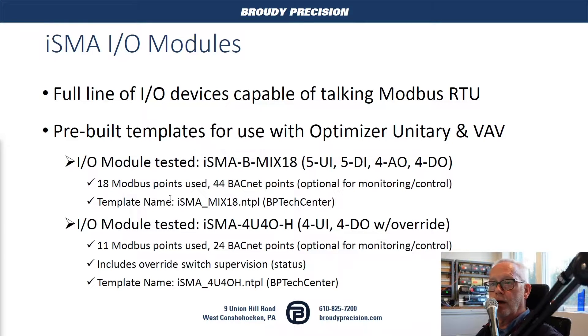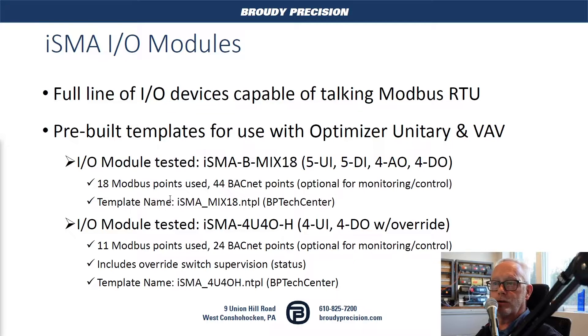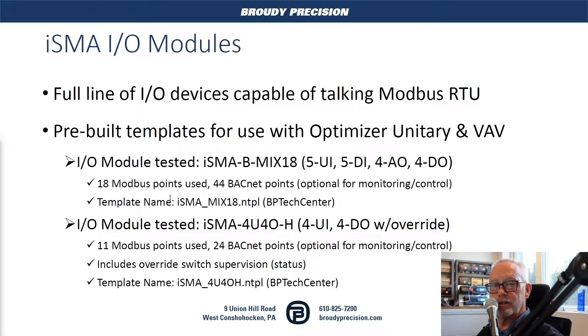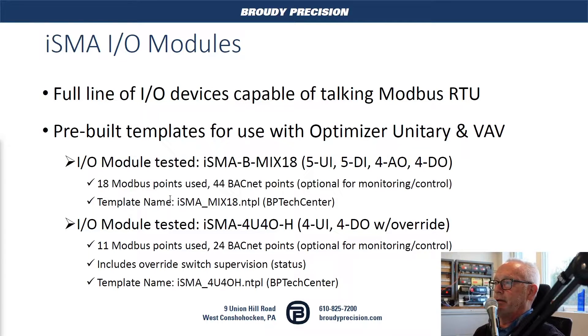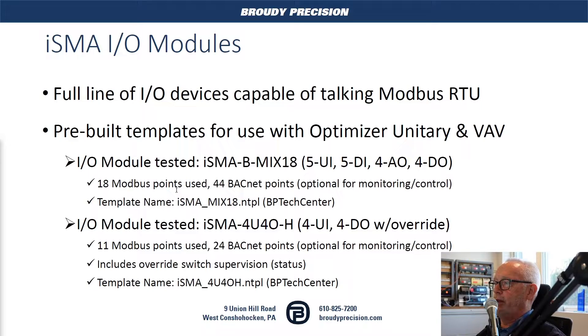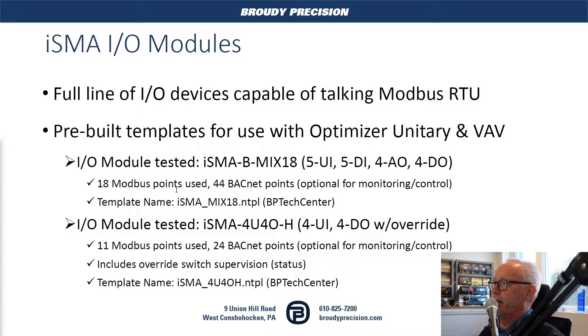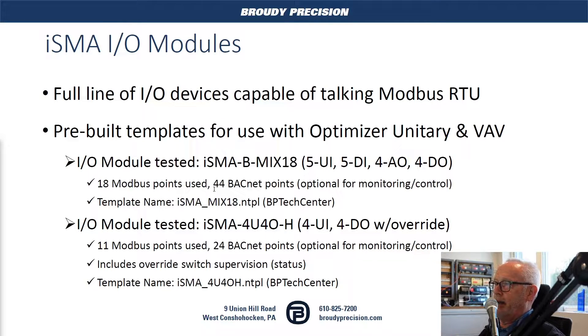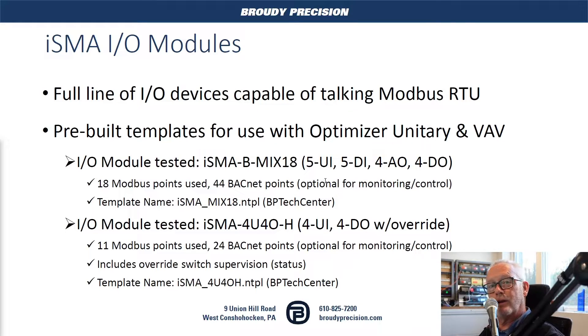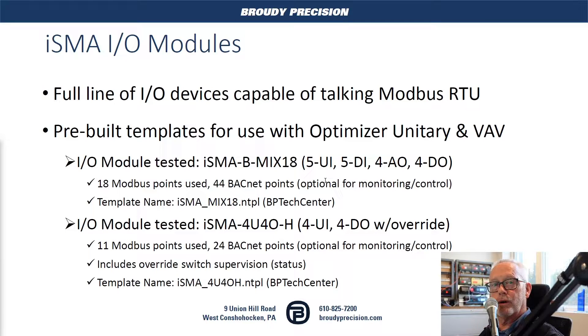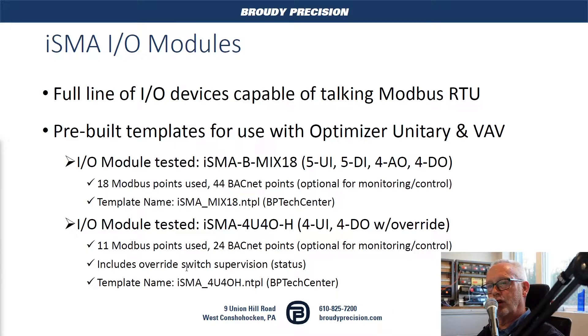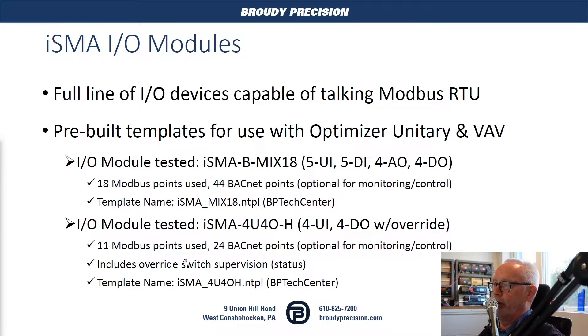What we've tested with these controllers has been the ISMA I/O modules. They have a full line of I/O devices capable of talking Modbus RTU, and we went ahead and pre-built a couple of templates for two of their devices. We picked the Mix 18, which is an 18-point mix of I/O, and also their 8-point module. In my application or in this template, we have about 44 BACnet points there that can be used for monitoring and control. They don't count towards the global capacity unless they're brought into the points folder of the controller for the station.